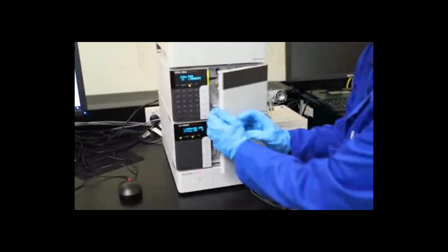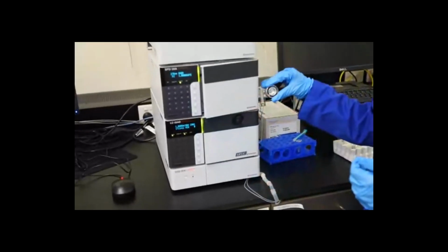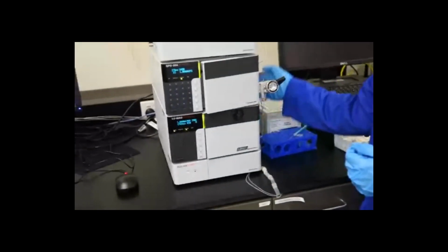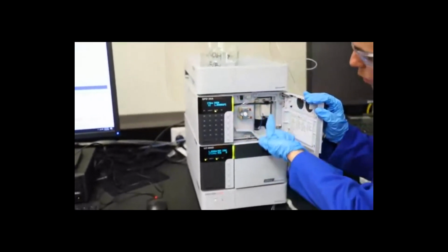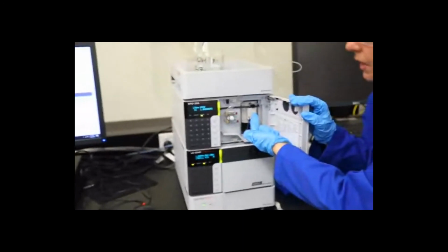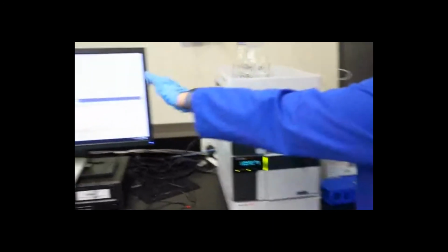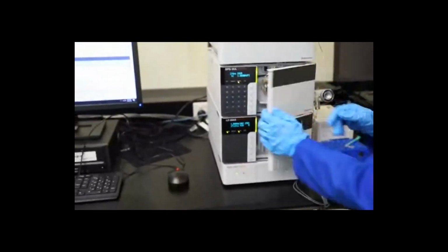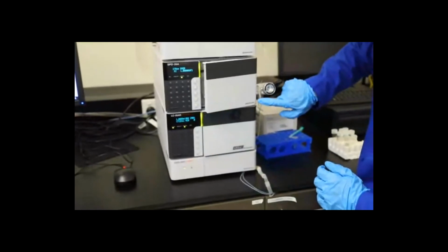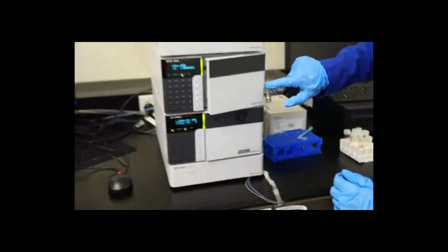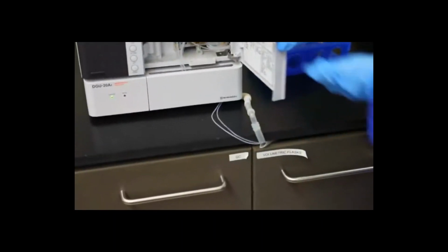From there, it moves around to here where your injection port is, comes up through the back here through our column, and then comes back into here where you've got your UV detector. From here, the UV detector detects to our computer screen here. But most importantly, we actually have two spots for waste. The first one is here where you inject. If there is any excess, it runs off into here. The second one, behind the machine, there is a pipe that comes down and it gets collected into our waste container.